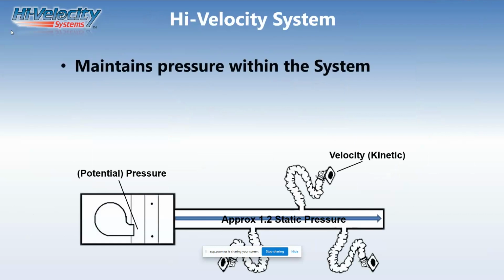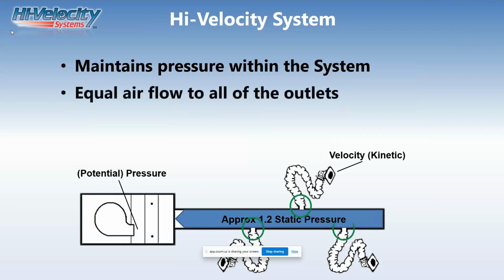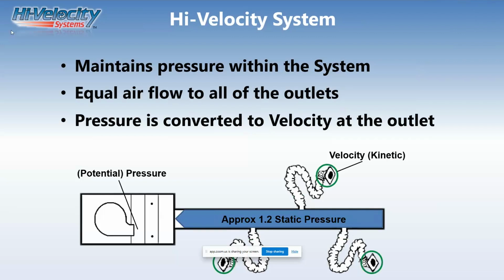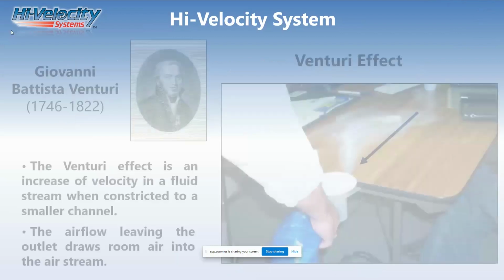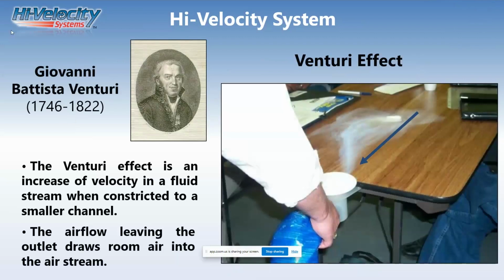Well, high velocity, definitely different. We're maintaining the static pressure in the ductwork. That means that every joint's sealed. We're maintaining the static pressure in the ductwork, and it's bouncing off the end cap back to the fan coil, maintaining that equal airflow to all the outlets. Now, the pressure that normally on a conventional system is created at the fan cabinet, well, now we're letting that velocity out of the outlet. And when that velocity comes out of the outlet, a simple principle of Venturi action happens.